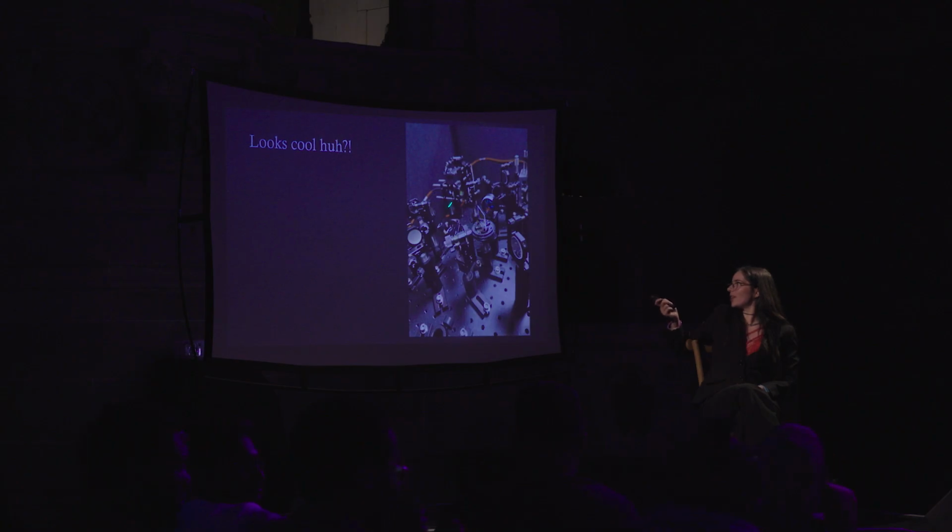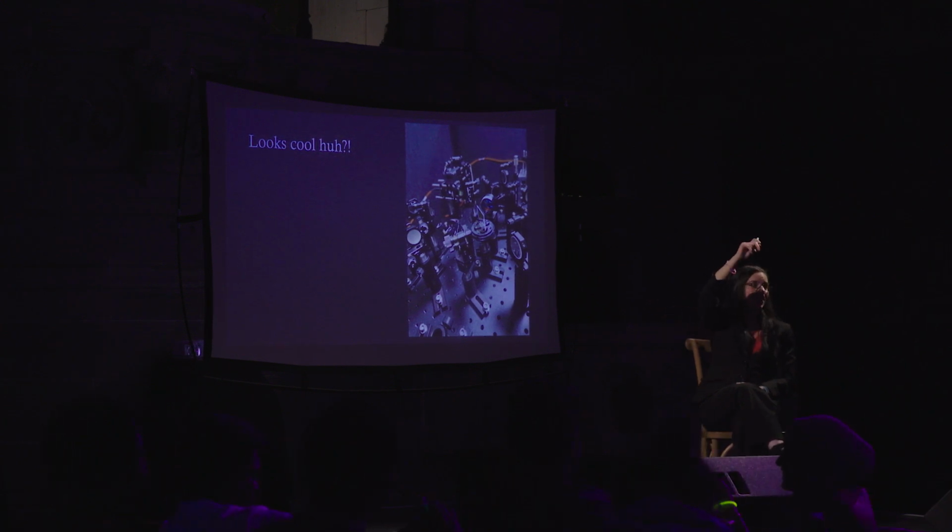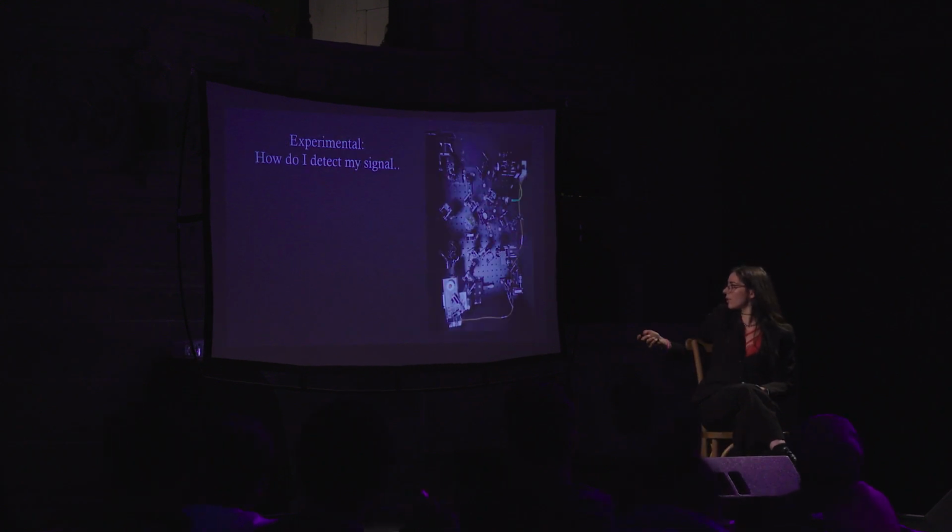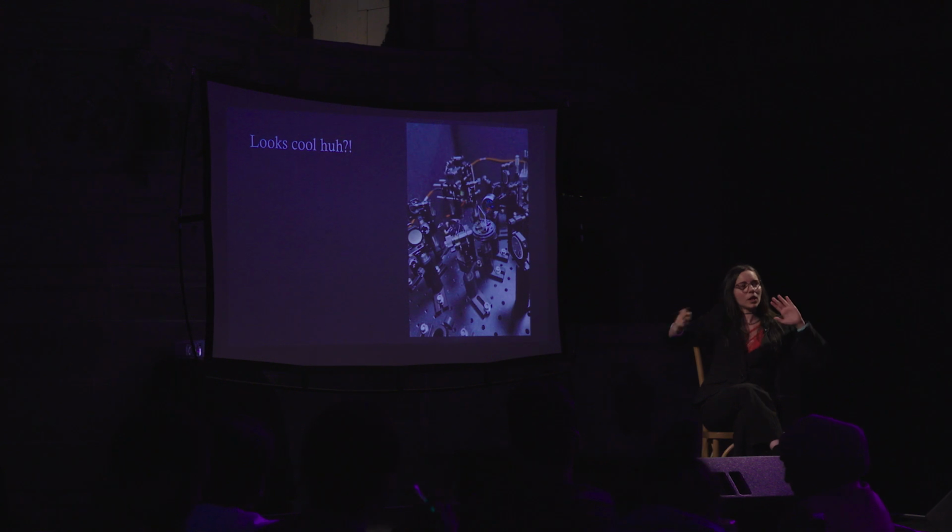This dichroic plate is to allow only the photoluminescence, like what you have right now. Let's say that you're excited and you have photoluminescence that you're giving me back. I want to detect that photoluminescence, and I don't want to detect the laser back, because that sensitive thing over here is gonna burn if the laser goes to that. So I only want the photoluminescence that comes from you, the sample that I'm using, to come back. So then this dichroic plate is protecting that.